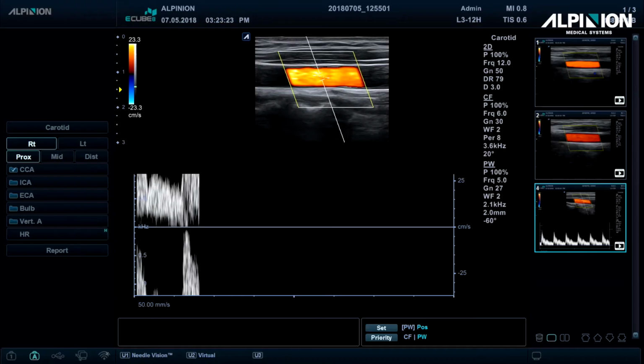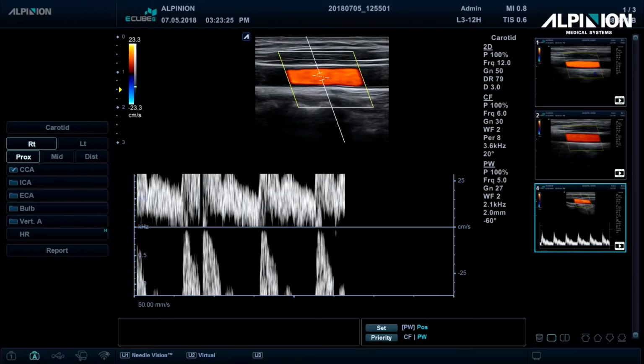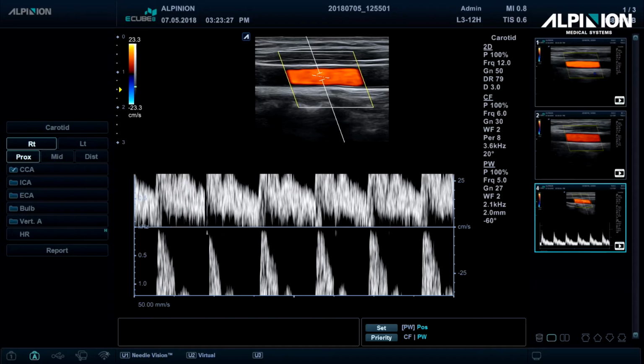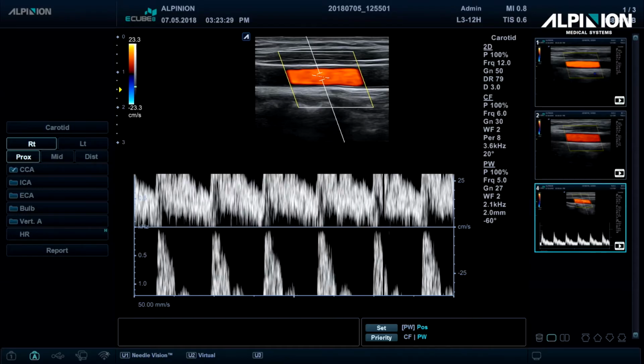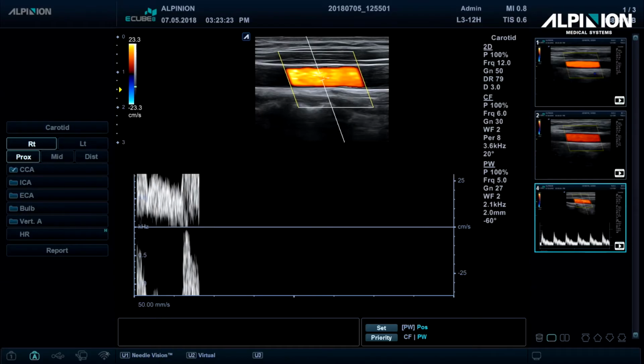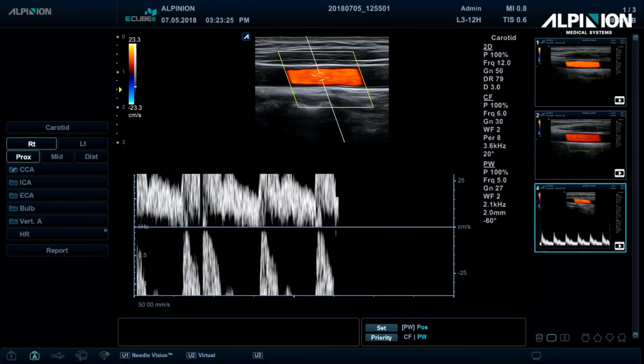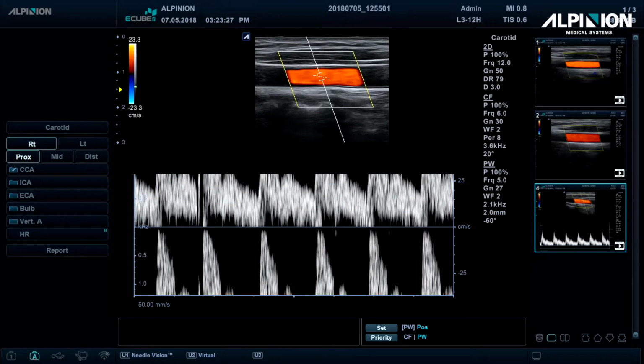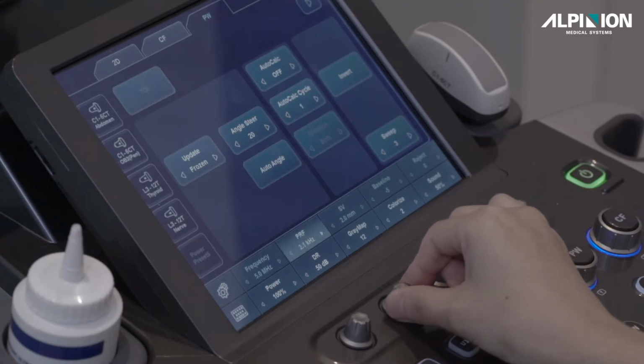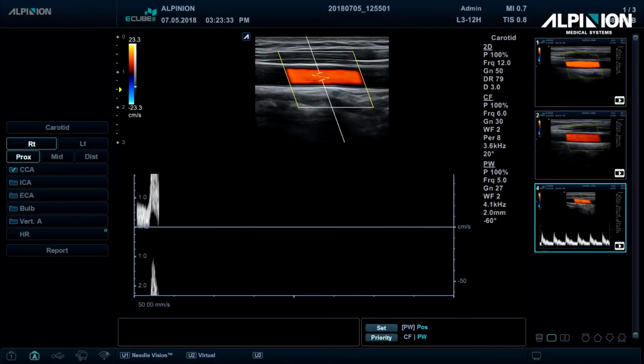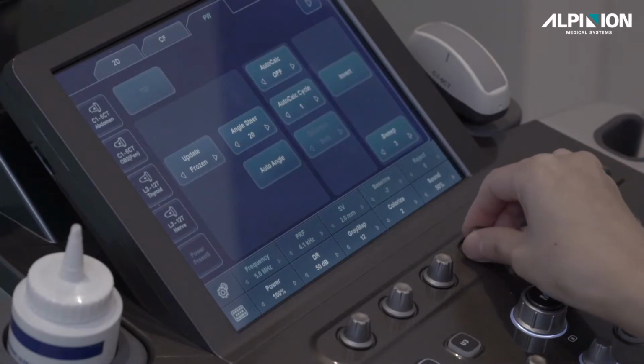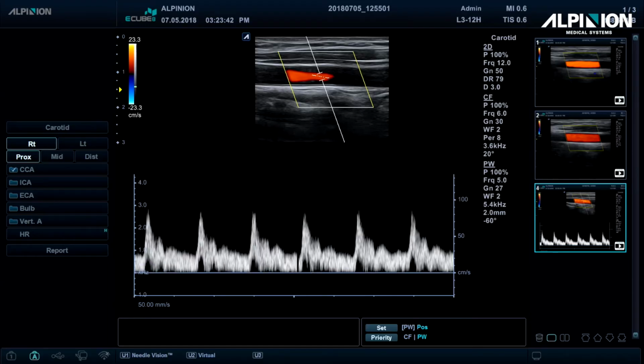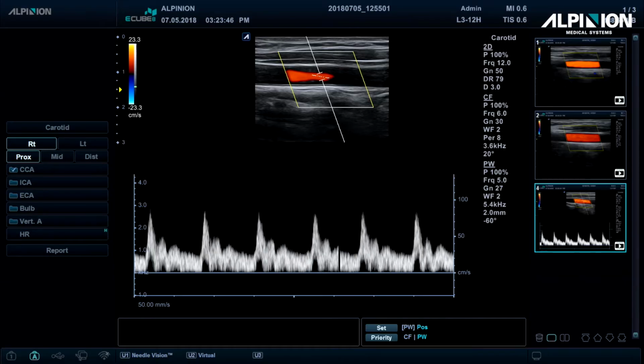In case that your examined blood velocity is too high over the program velocity scale in Doppler, aliasing artifact can occur and the peak spectrum will be displayed on the opposite side to the real direction of flow. In this case, you should adjust the PRF parameter to increase the maximum velocity scale in your spectrum. Also, you can adjust your baseline with this fourth rotary key as well. In this way, you will be able to get rid of an aliasing artifact in PW spectrum.